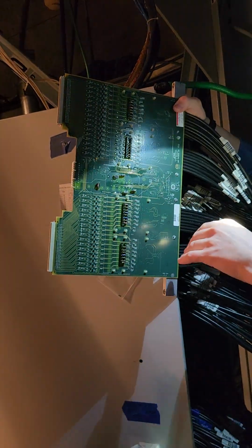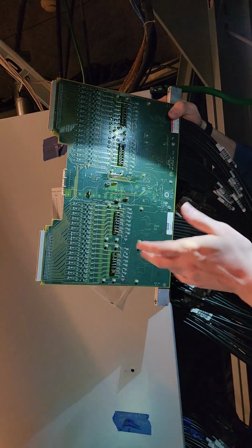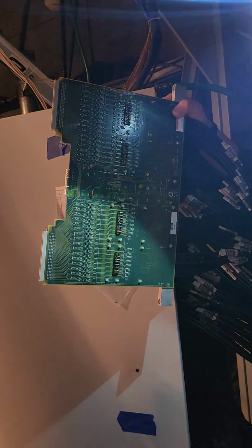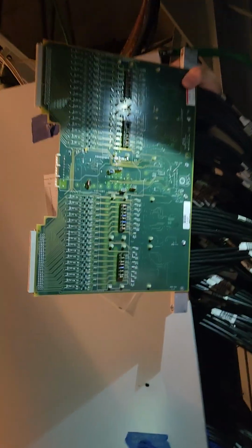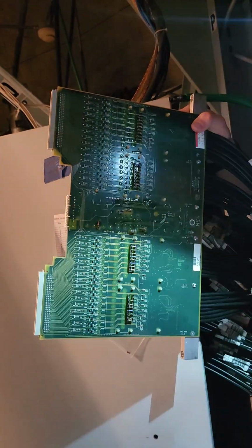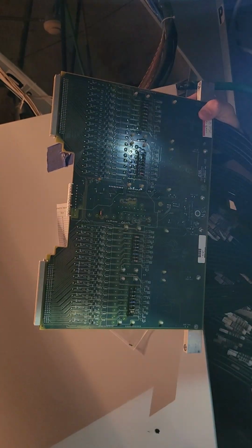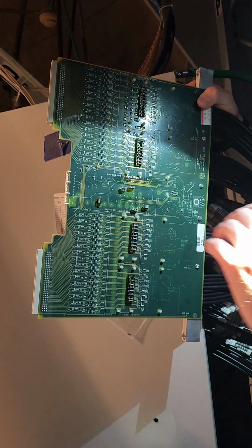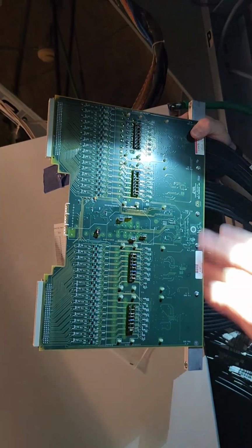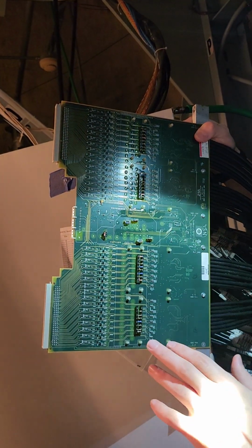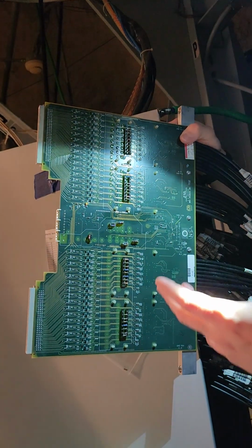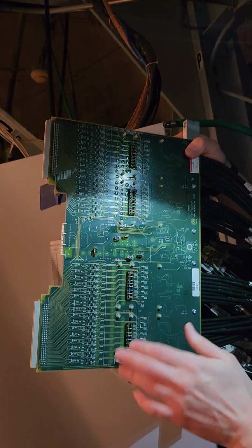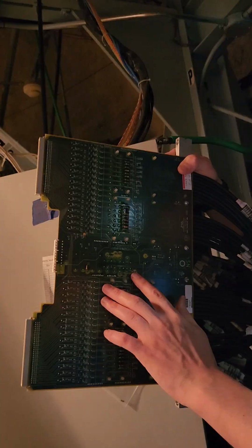When our tubes go bad, and they do, when we're running, we lose 3 to 4 PMTs a month. A month? And when they do, instead of sending a signal back, they'll send down what we call breakdown pulses. This is a whole bunch of charge that goes back up the stream and can potentially damage these feed resistors. So if you have a PMT go bad, it'll end up damaging one of these resistors here and let it go. If there's still charge to dissipate, if the breakdown still needs to continue, the next thing it's going to hit would be the resistor that feeds the group of 8.